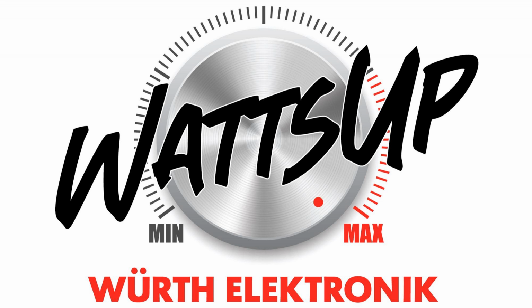And during the test, also the current is monitored to see if there are some sparks or some current leakage in the windings, which could be an indicator of having a fault inside the component.